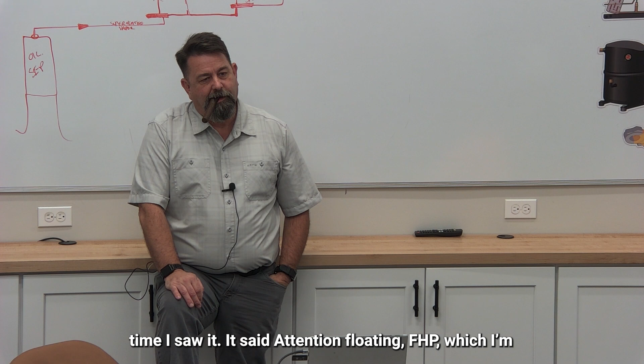Yeah, so I took a picture of it, because that was the first time I saw it. It says "Attention, floating FHP," which I'm assuming is floating head pressure. This rack has been converted to operate with floating head pressure, all bold and underlined. The subcooler EPR is set to evaporate at 35, the large set comes in at 85, and so on. The controller input is the drop leg temperature sensor. There you go. And then highlighted: please do not alter these settings.